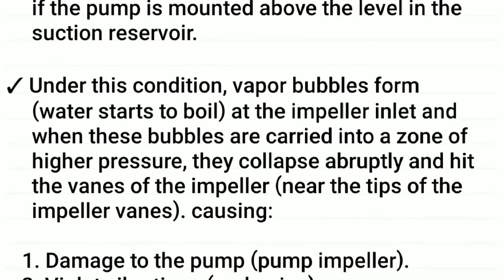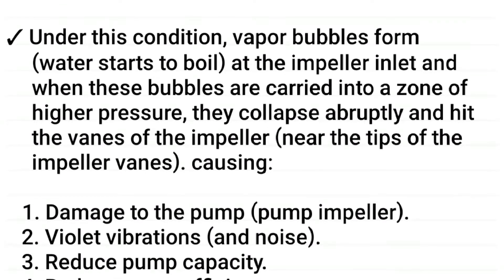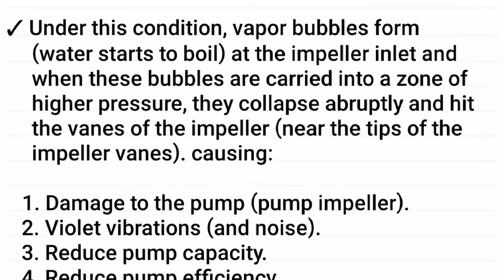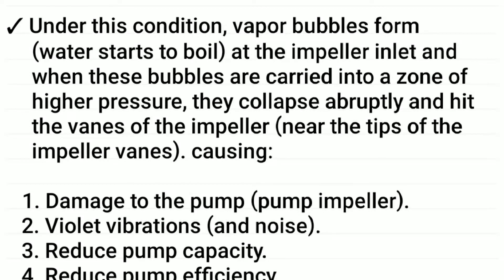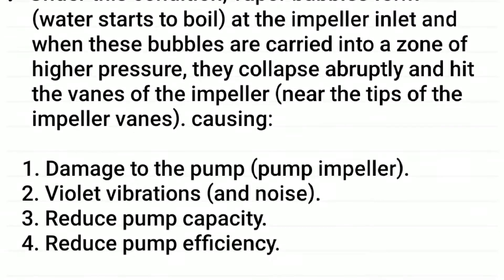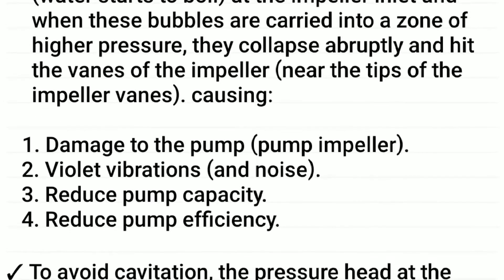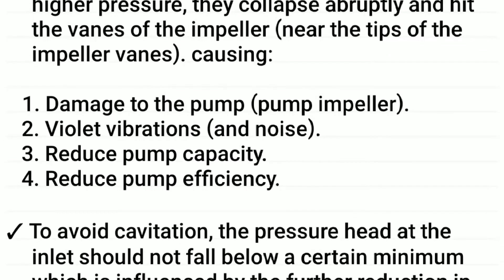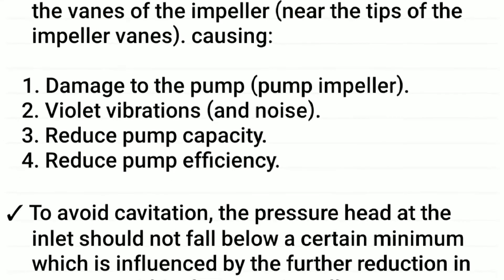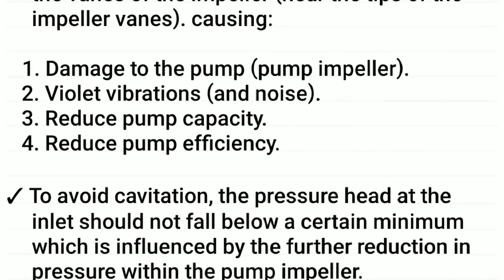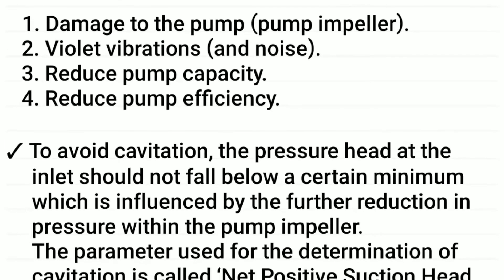Under this condition, vapor bubbles form as water starts to boil at the impeller inlet, and when these bubbles are carried into a zone of high pressure, they collapse abruptly and hit the vanes of the impeller near the tips, causing damage to the pump and pump impeller, violent vibrations and noise, reduced pump capacity, and reduced pump efficiency.